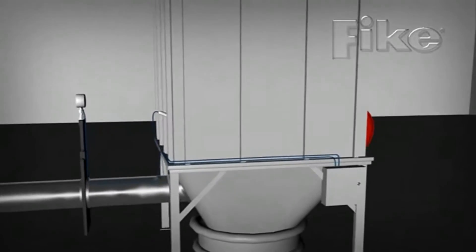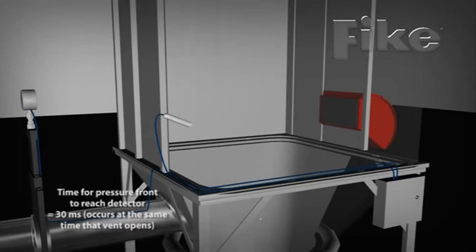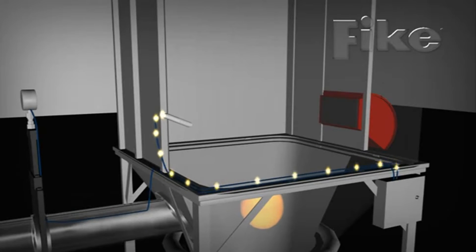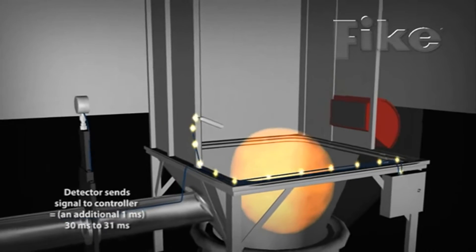It is also necessary to isolate the deflagration, preventing the transmission of the flame into interconnected vessels. As the fireball grows, the detector rapidly captures the pressure spike and sends a signal to the control module, which tracks the pressures, capturing four readings every millisecond.